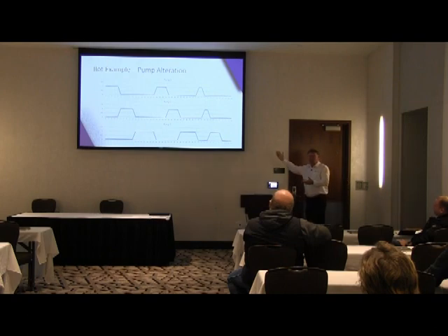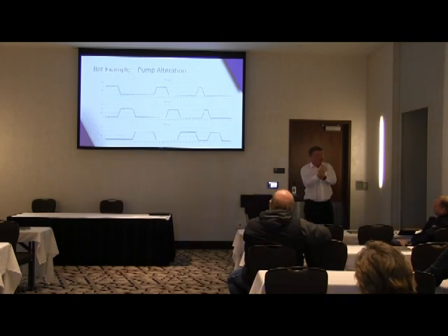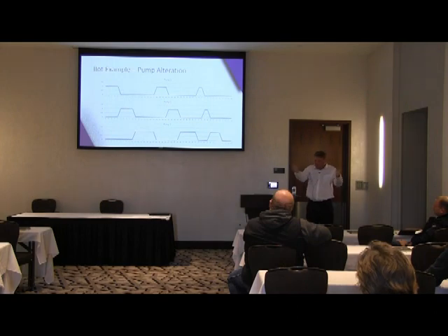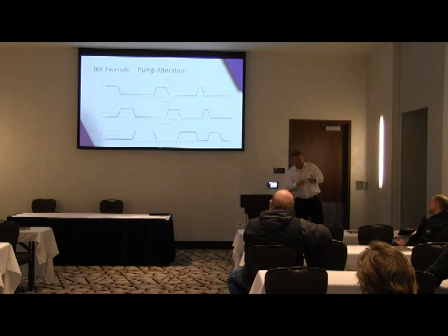So really, the first application of this was, when we see patterns like this, notify. We're gonna send a work order. We interface with the maintenance system, send a work order, send someone out there. The next thing they figured out was, well, he collects a little bit more data: temperatures of the bearings, amp draws, water flows, or whatever.